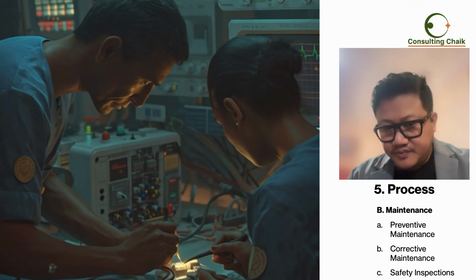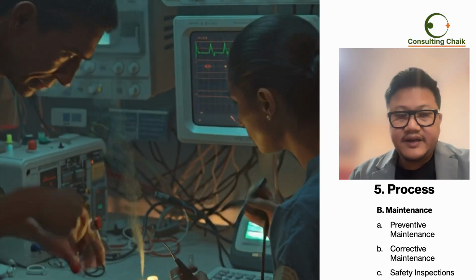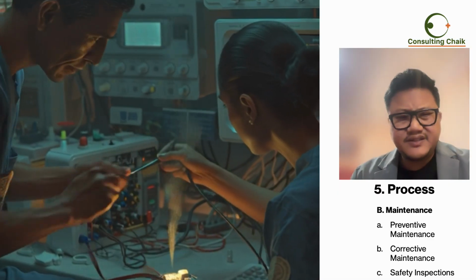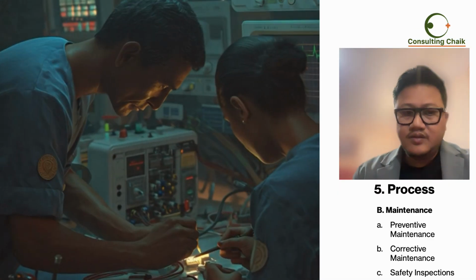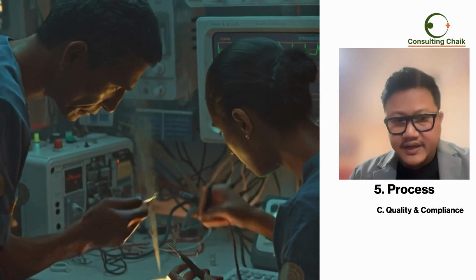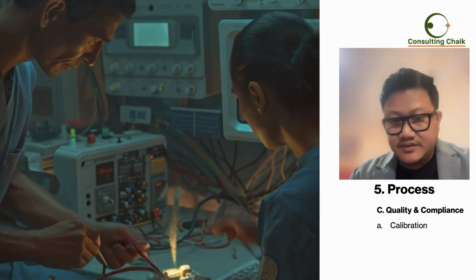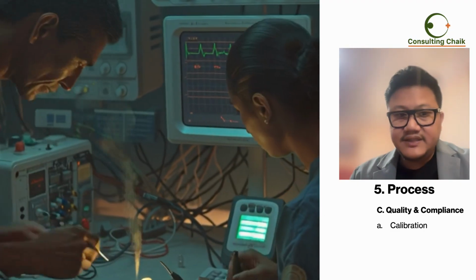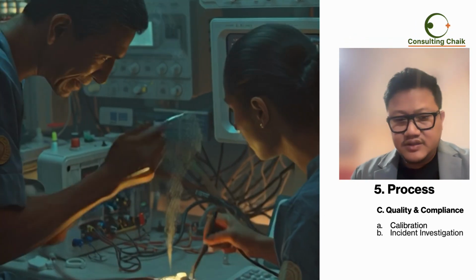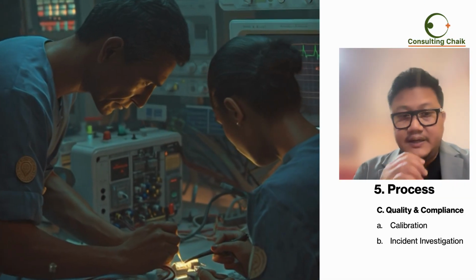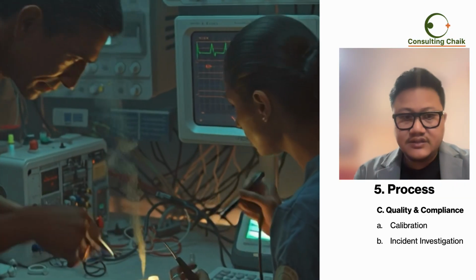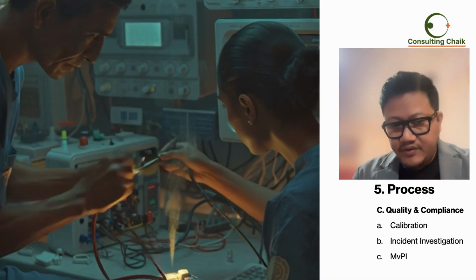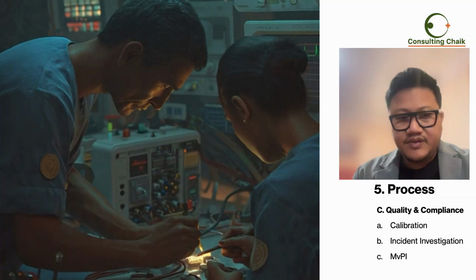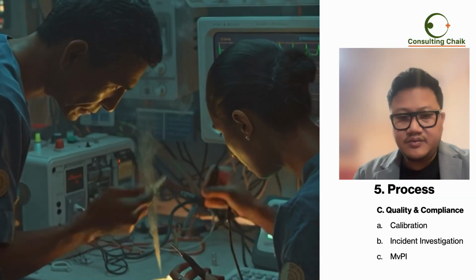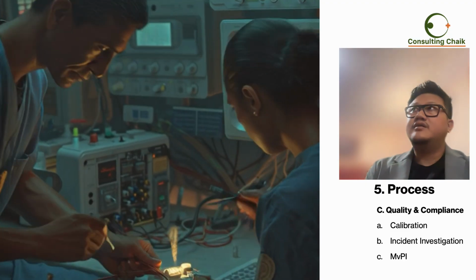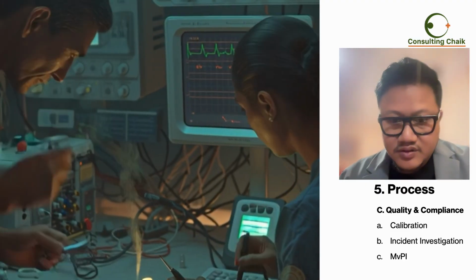Then comes your safety inspections. So annual electrical safety, your leakage test, visual inspections, time to time visual inspections that you do, all this. Then comes your quality and compliance. So here your calibration. So it's traceability standards for pumps, ventilators, monitors, your incident investigations. So device related any adverse event, root cause analysis, and reporting to MvPI. Okay, so MvPI, as we know, it's a body where you need to report for any kind of major equipment issues. Okay, you have to register it.